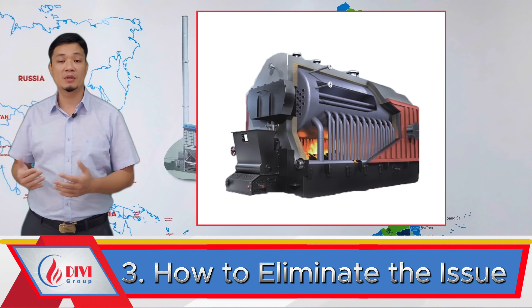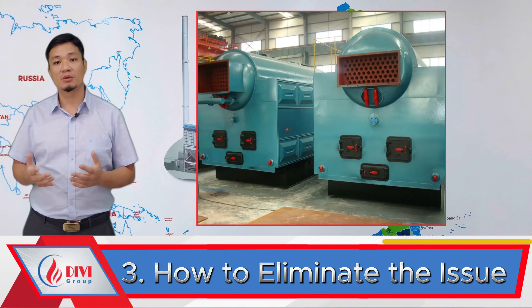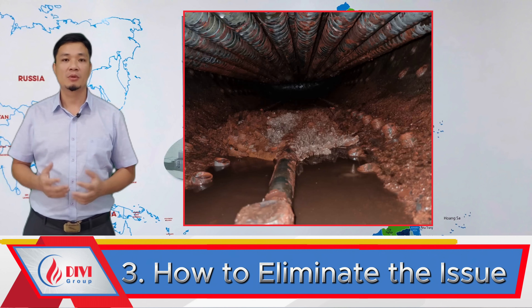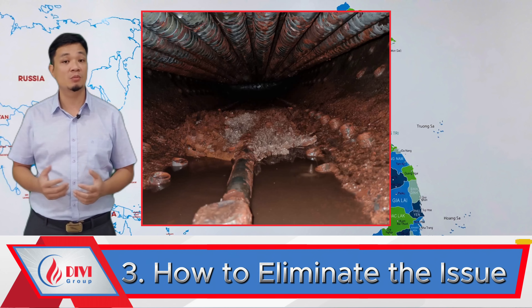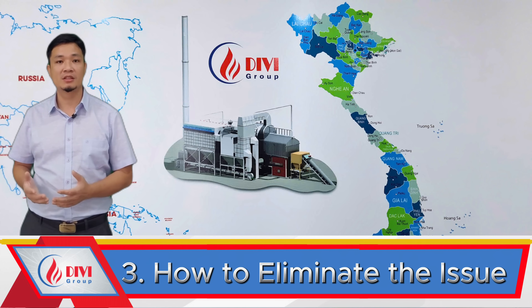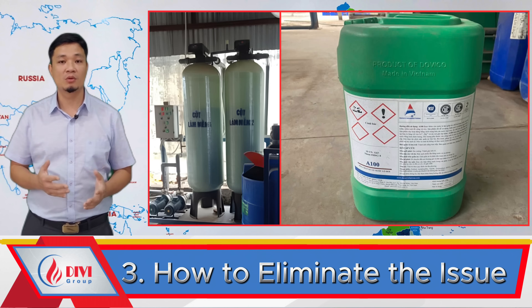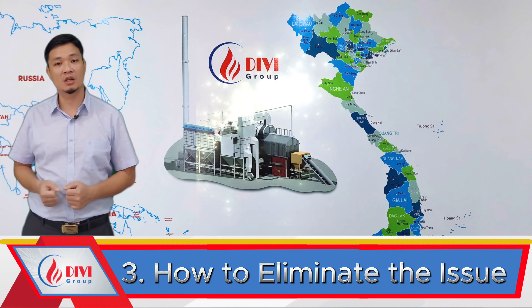Part 3: preventing the same problem. This type of failure is common in belly-fired boilers. If you're using this design, please take note of these preventive measures: regularly clean scale deposits inside the boiler, especially at the steam drum area beneath the fire — ideally weekly or bi-weekly, the more frequent the safer. Consistently use water treatment chemicals to minimize scaling.